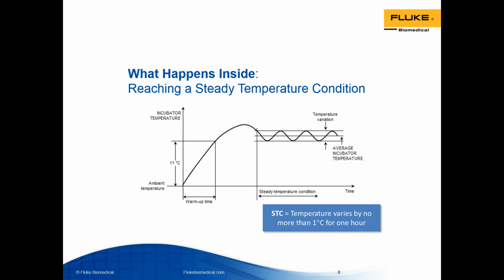So when we first turn on the incubator for a test, it should be at room temperature or ambient temperature. And the time that it takes for the incubator to warm up to 11 degrees Celsius above whatever your starting temperature is, is called the warm-up time. So say my ambient temperature is 20 degrees Celsius. However long it will take my incubator to get to 31 degrees Celsius is then considered my warm-up time.